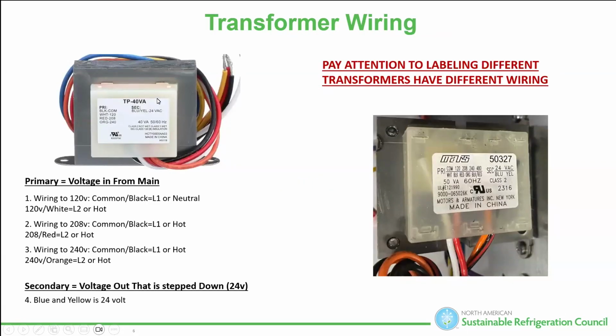Transformers are a function of magnetic fluxes, but we have multi-taps. How much of the windings am I going to use? How much of this transformer? By having a multi-tap, I have a single core with different taps off of it, and based on how much of that core I use and where I tap the wire is where I'm stepping down my voltage.